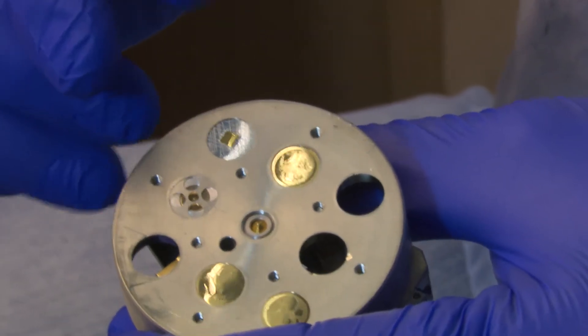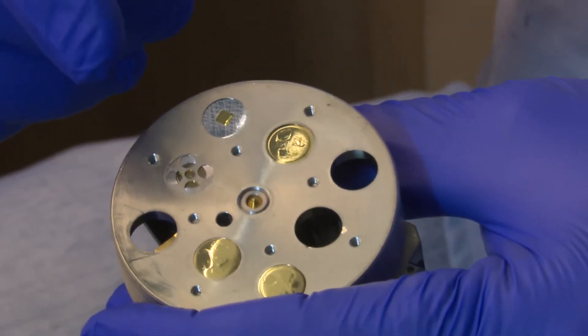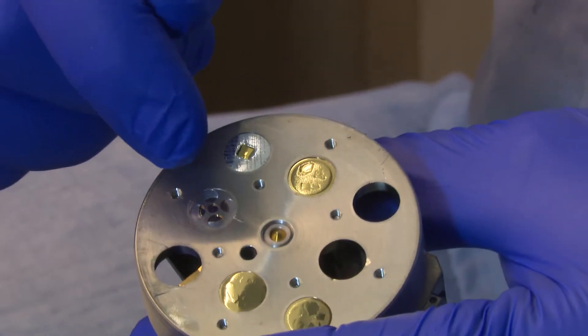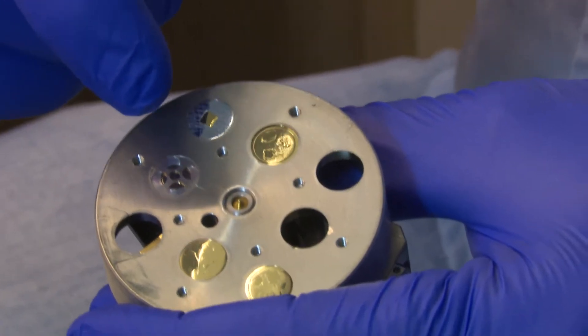What sort of scales and sample preparation need to be done? This instrument is very demanding on its sample requirements. Samples have to be very flat, with a very good polish on them if possible. They have to be round samples — these are on 10 millimetre round discs. The samples have to be electrically conducting, so if they're insulators naturally we put a gold coat or a carbon coat on them.